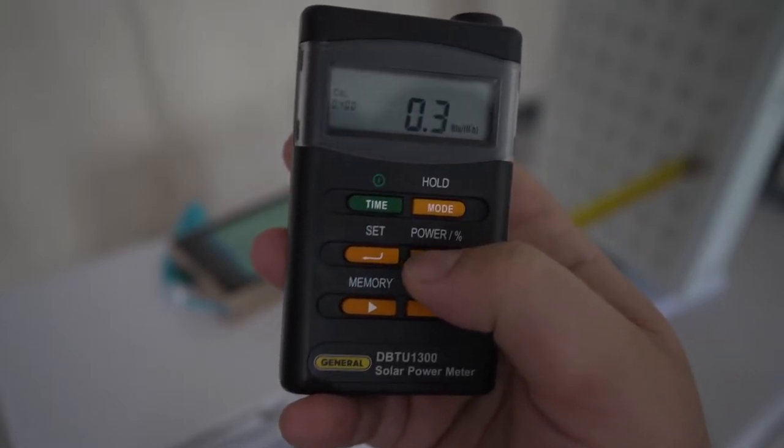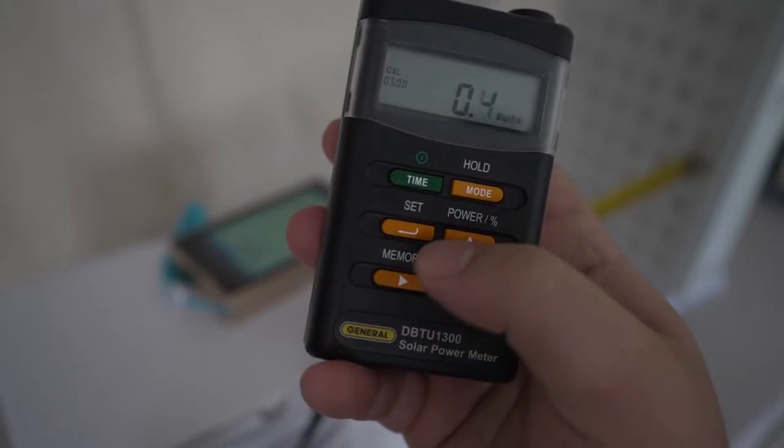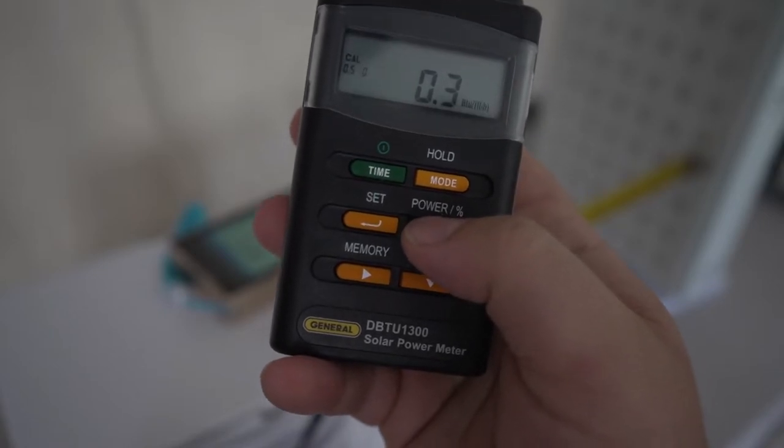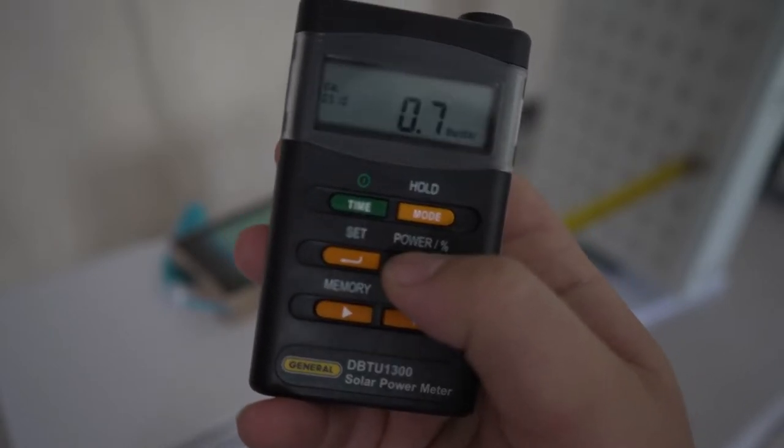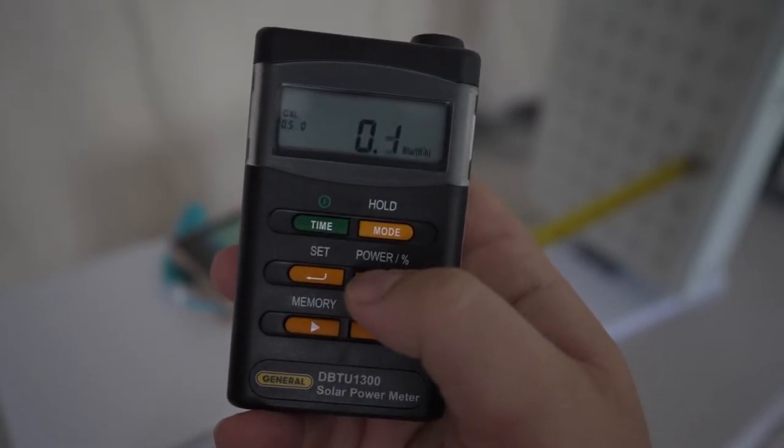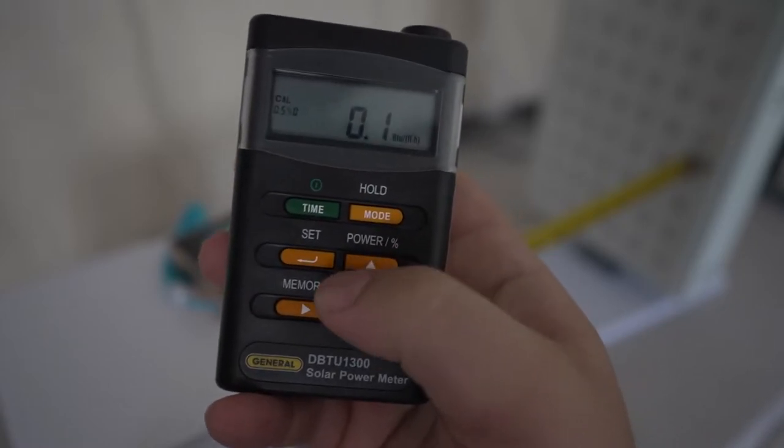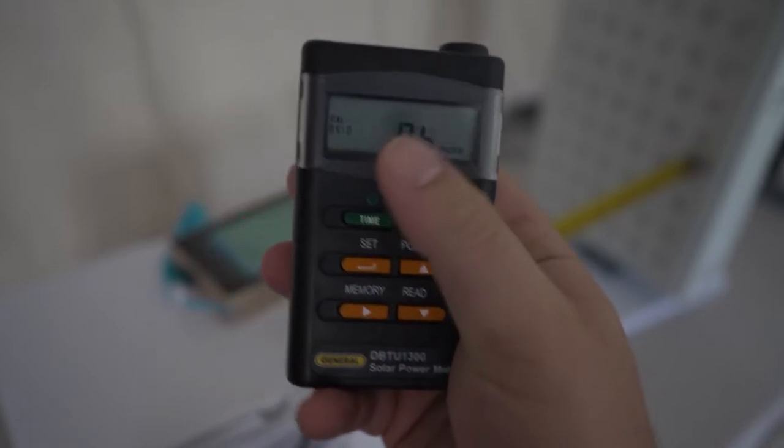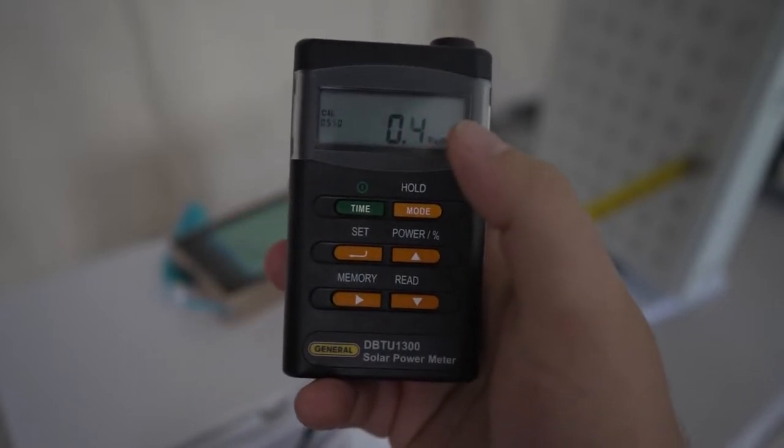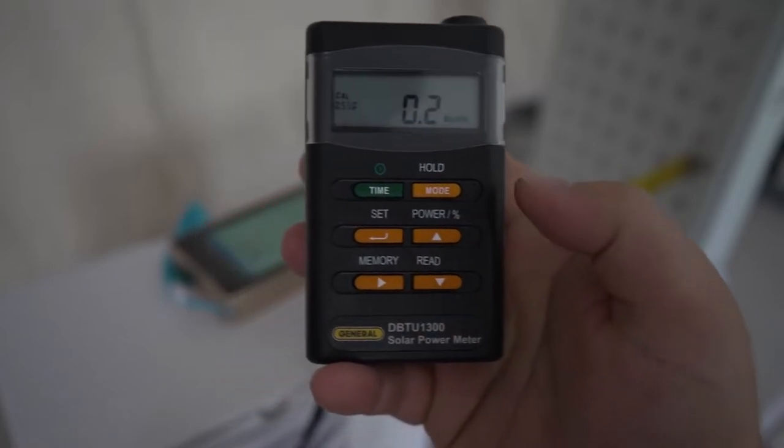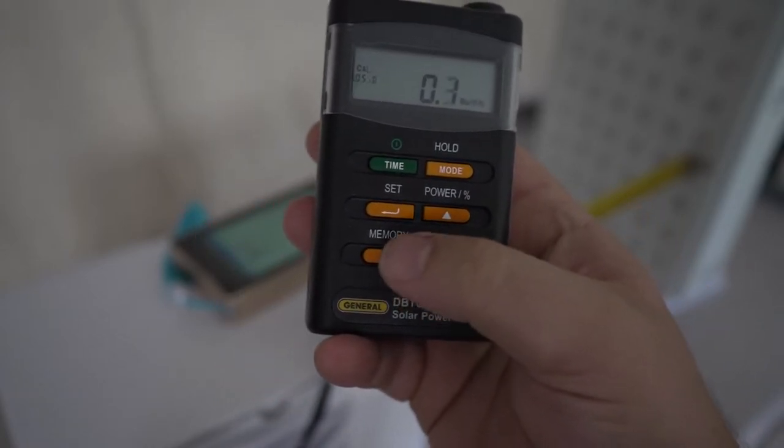So we go through, we set it to 0.55. And this is a dangerous calibration because I could increase the sensitivity and give you even more falsely high numbers. So companies using this technique could actually really falsely inflate their numbers because they can recalibrate the number and do 2x or 5x or something crazy.